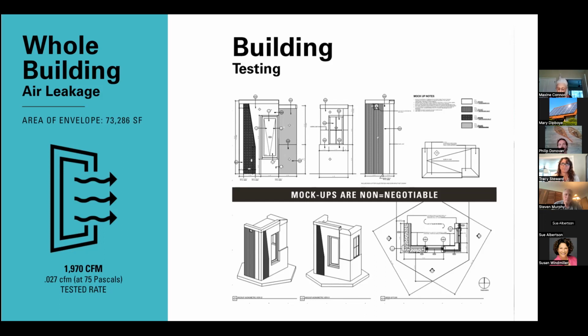NeoCity Academy has over 73,000 square feet of building envelope, exterior walls and roof and windows. We set an air leakage rate of 0.15. That's lower than code, which lets you leak 0.4 cubic feet per minute out of the envelope. Army Corps of Engineers says let's do a little better, that's 0.25. Working with CMTA, they said if we want to get to zero energy, we want to lower it down to 0.15 cubic feet per minute.